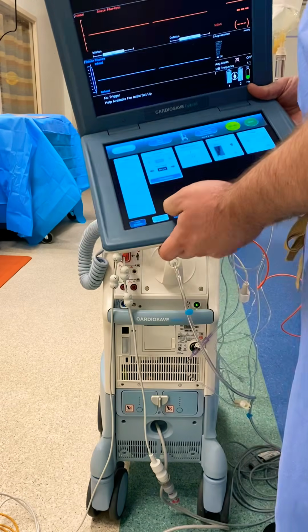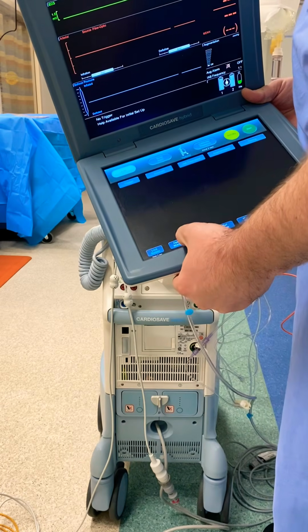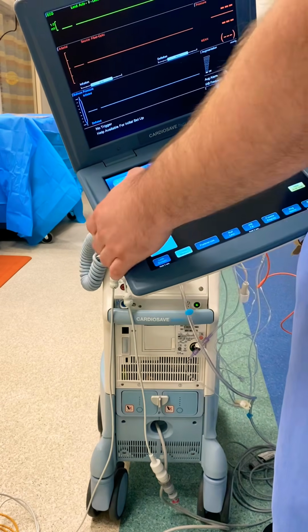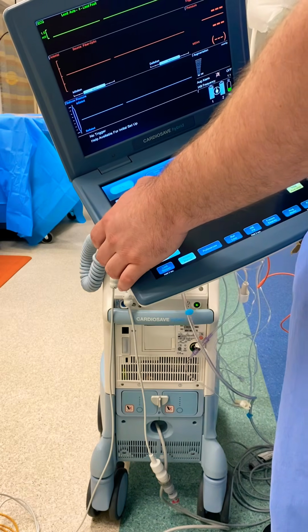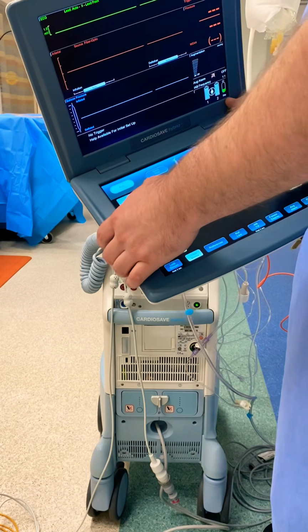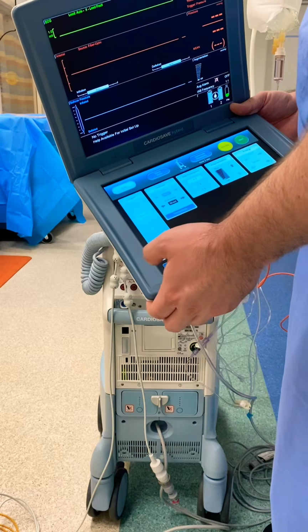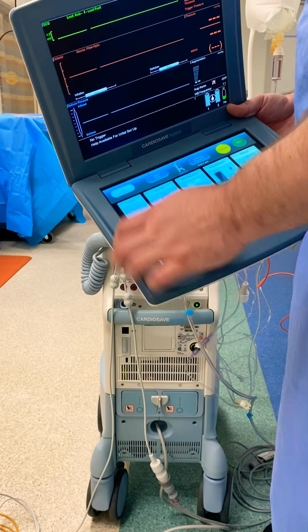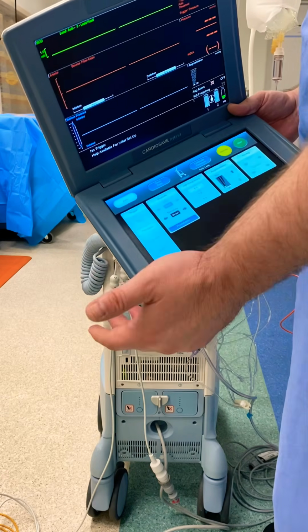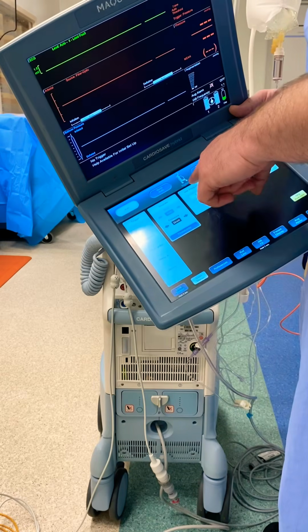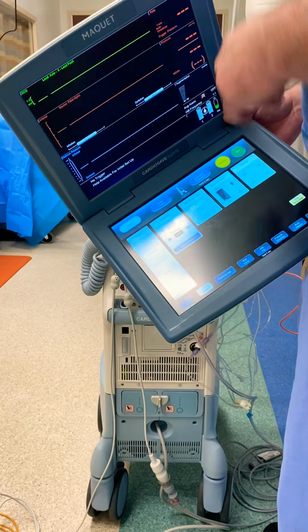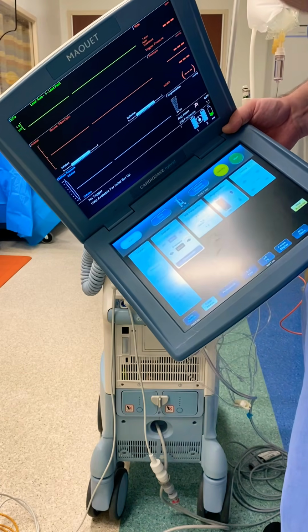So when I hit open all menus is what I did. It's going to show that normally the EKG is connected and it will be on ECG as our trigger, and our frequency is automatically on 1-to-1. This is going to be in automatic mode. That is where we leave it.